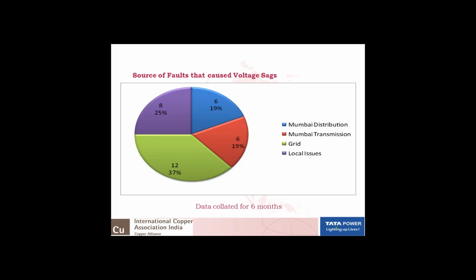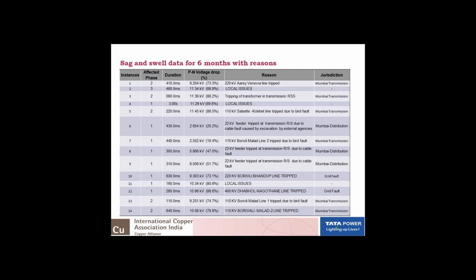Now we further analyzed this data, and we found that in one instance, 2 phases were affected. The sag was for a duration of 410 milliseconds. The voltage dropped to 9.204 kV, that is 73.3%. And the reason was the tripping of a 220 kV line. While this consumer is fed at 22 kV, a tripping of a 220 kV line in the Mumbai transmission system was the basic cause of this voltage sag.